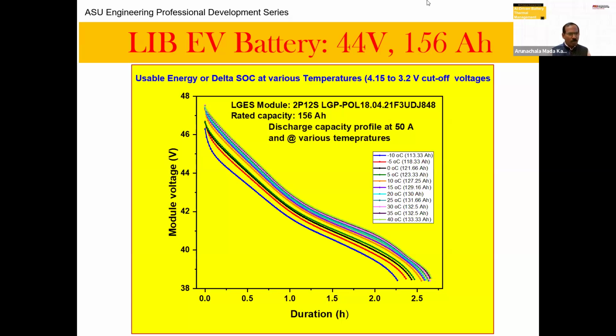Especially when you're operating below minus 5 degrees Celsius, there can be lithium forming between the electrodes as a dendrite, or in other words, battery cells will start electrically shorting internally. So the internal shorting is exactly same as external shorting. High voltage cells, high power cells with larger capacity - if there's a chance for external shorting or internal shorting, it is going to be a catastrophe. That's a real thermal runaway.